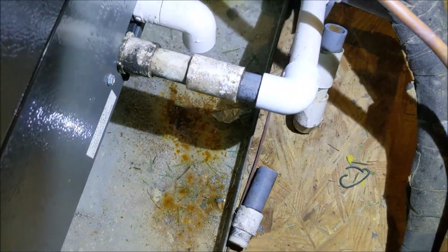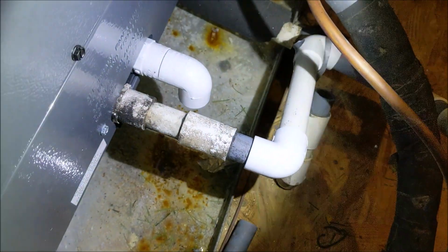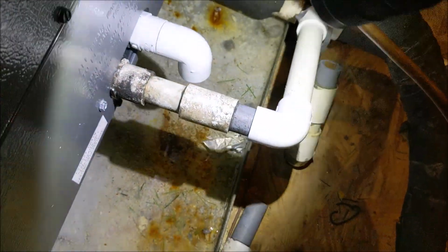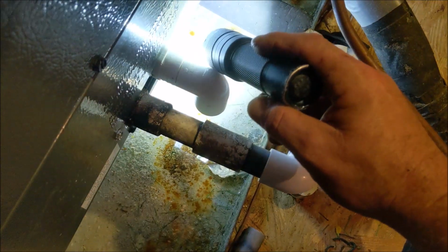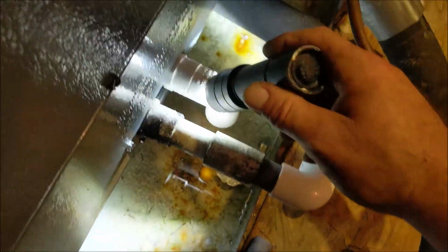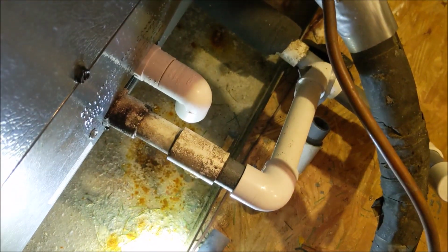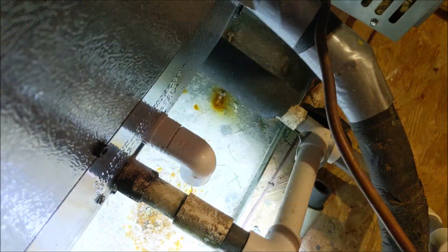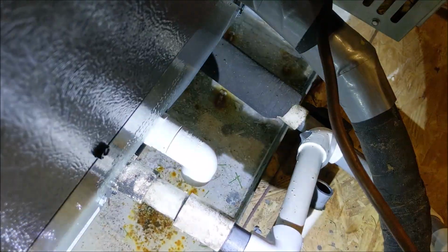Now, if you notice, this evaporator coil doesn't have what they call a float switch. Remember I showed you the other one had a little black wire? If they put a secondary float switch on this side, because you can get a primary float switch, a secondary float switch, and a pan float switch, and if any one of those three senses that water and feels it clogging, it would shut down. You wouldn't have this condition.